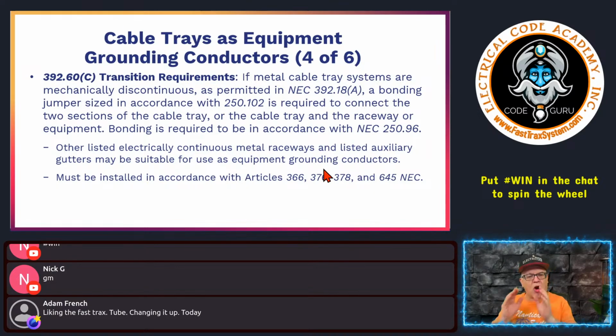except they are, in most cases, going to be a raceway, and again, you're still going to bond them. You're still going to be following the rules in 250.96, unless those wireways or gutters contain service conductors. And then again, if they're service conductors, then you have some things you have to follow in 250.92, right? Because they contain service conductors. So again, we talk about all that in grounding and bonding.